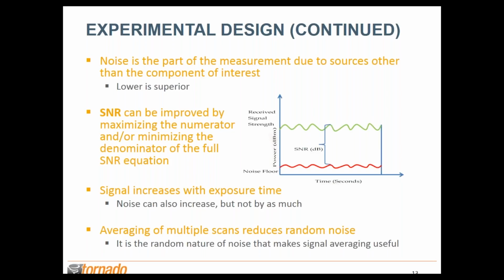As we increase the signal, and of course there ultimately is a limit there, we want to make sure we don't at some point oversaturate the detector or reach areas as we approach detector saturation that can create nonlinear properties in the data. But once we've maximized our ability within a good exposure, not saturation, in the linear range of the detector, we want to improve our SNR further.